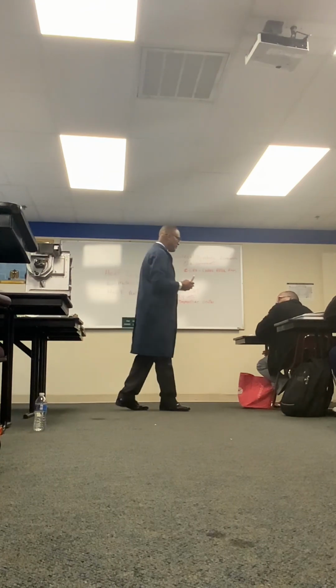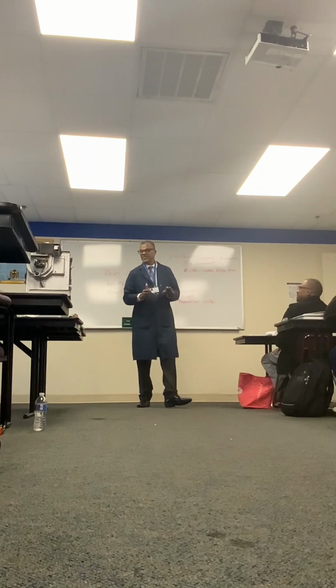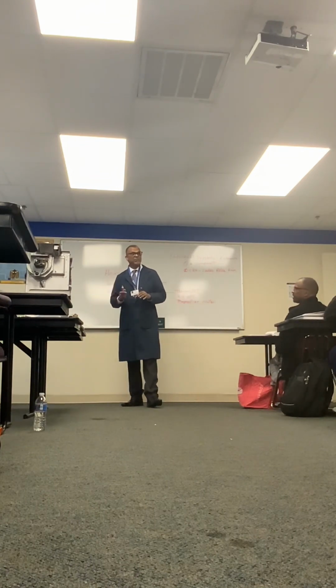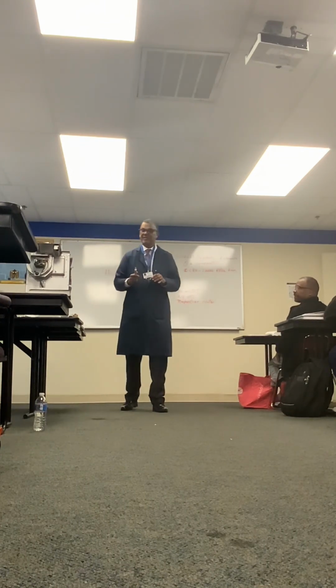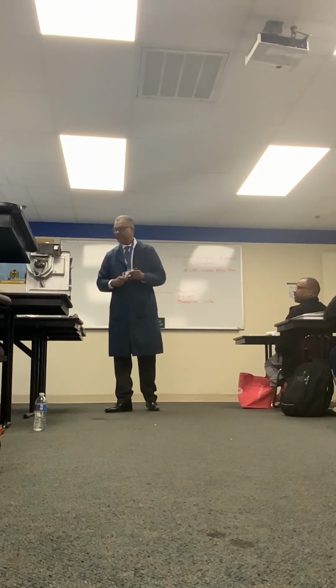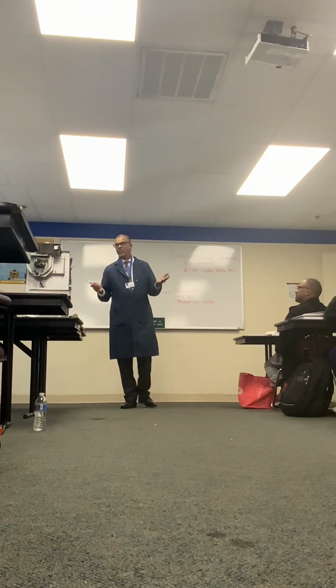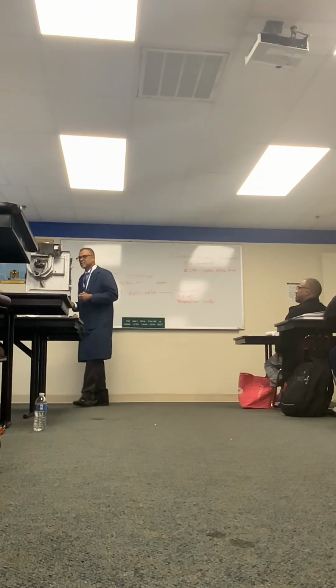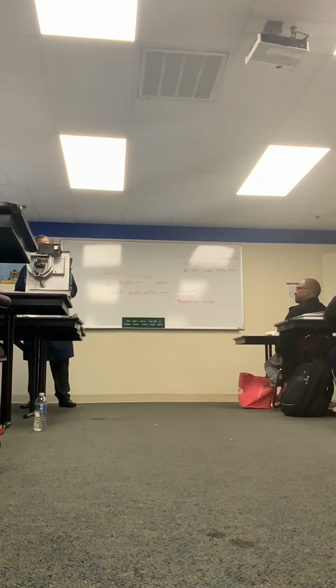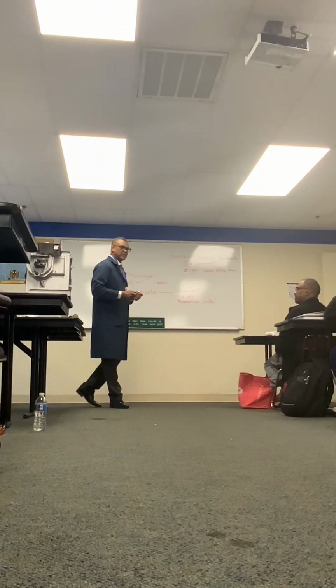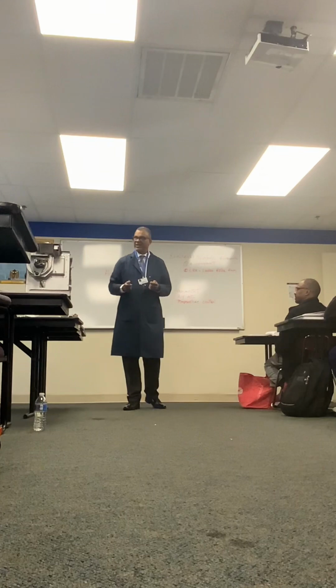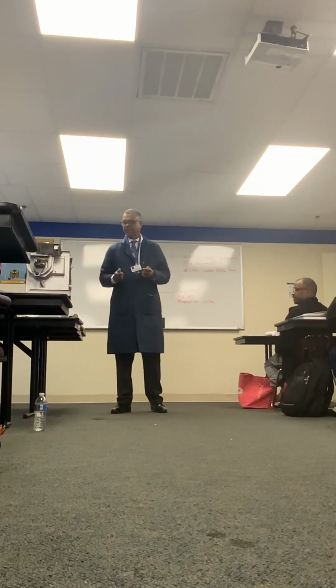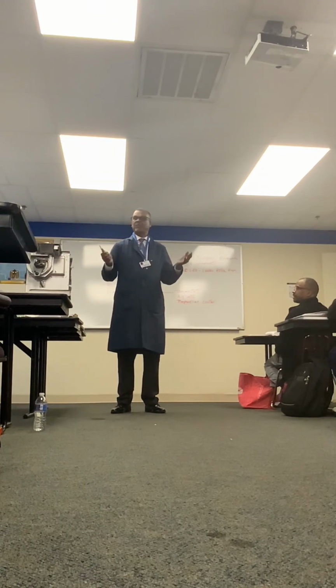For shock? Yeah. Now we hope it's not shock. What? You brought it up. Overflowing. What's overflowing? The water. Where does water come from? The evaporator coil. The evaporator coil? Yes. Why would water be on the evaporator coil? It's coming from the evaporator. Why? Because it's sweating, condensation. Why is it sweating and condensate? Where did that condensate come from? The heat that it is taking up.